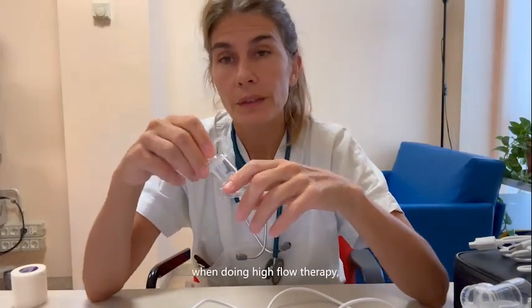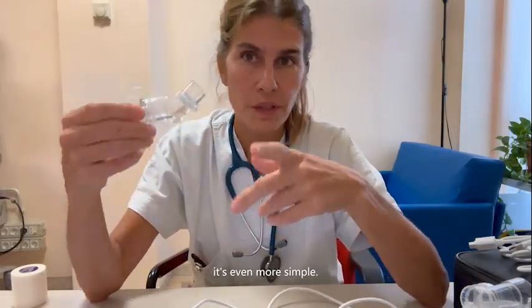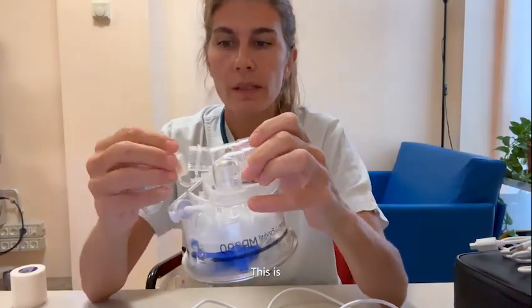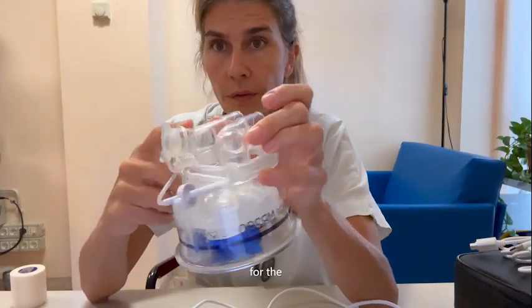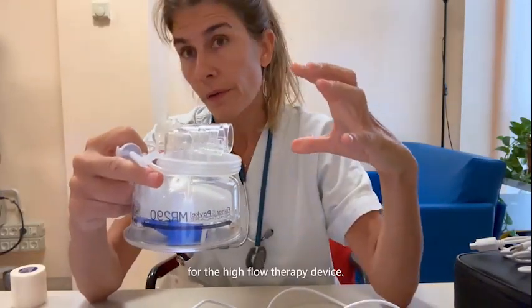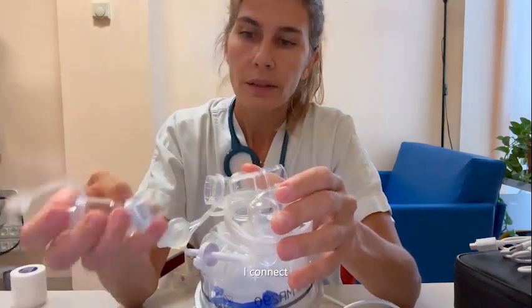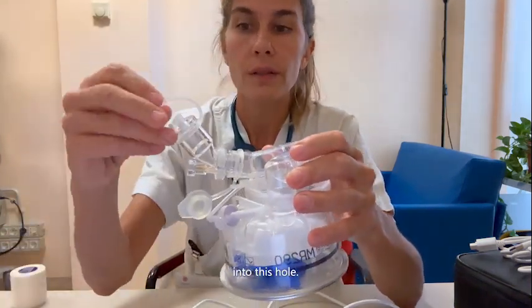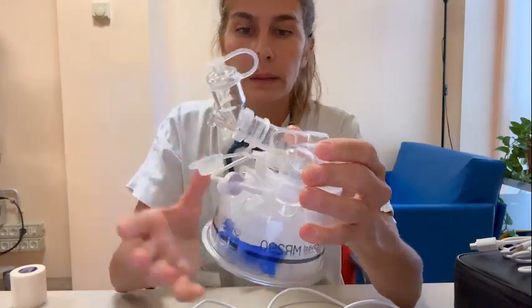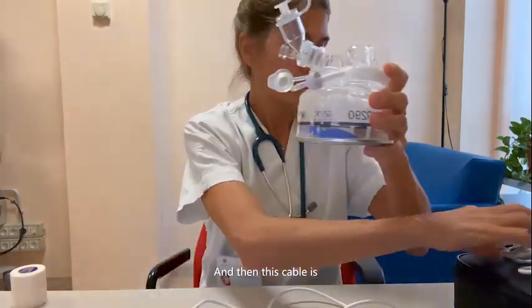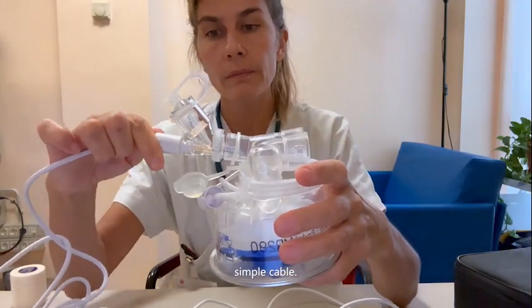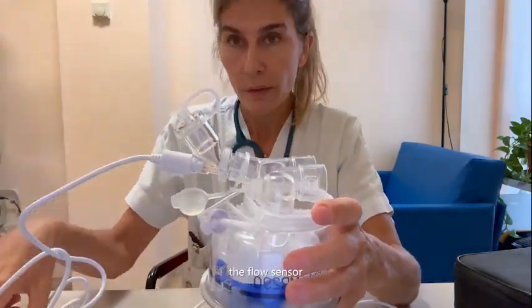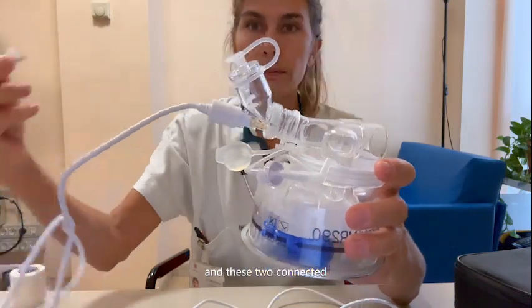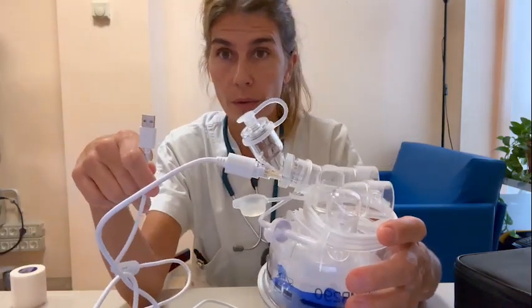On the other hand, when doing high flow therapy, it's even more simple. I do it this way. This is the dedicated connector for the high flow therapy device. I connect the medication cap into this hole, and then the cable. This cable is a simple cable since we are not using the flow sensor, and these two connected to the intelligent control, and that's it.